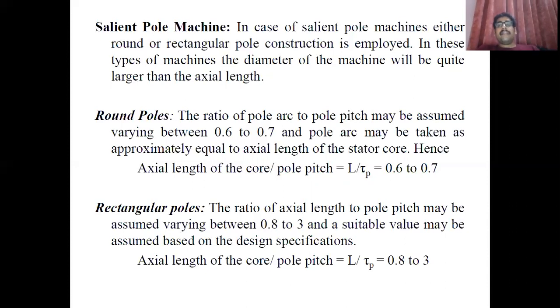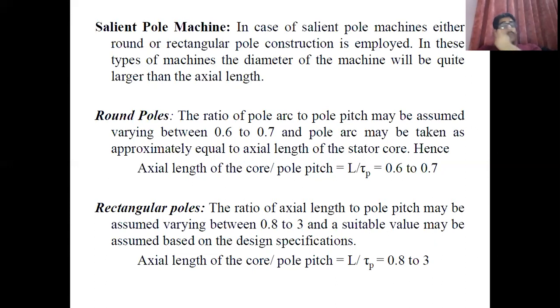To separate L and D, you have two conditions. If the synchronous machine has round poles, this ratio L/τp lies between 0.6 to 0.7 — meaning the ratio of pole arc to pole pitch may vary from 0.6 to 0.7; in some cases this value is taken as L = τp, i.e., L/τp = 1. Whereas in case of rectangular poles, the ratio of axial length of the core to the pole pitch equals 0.8 to 3.